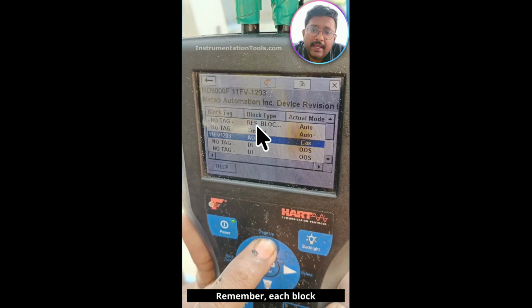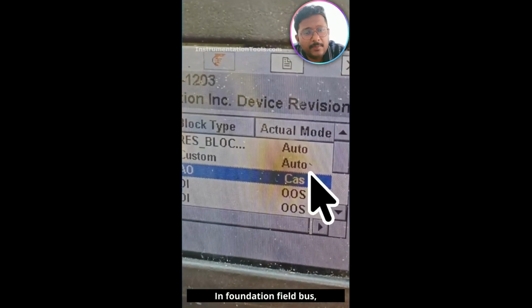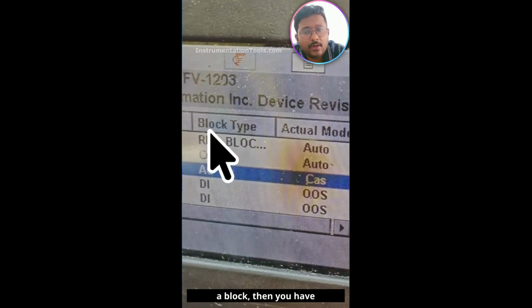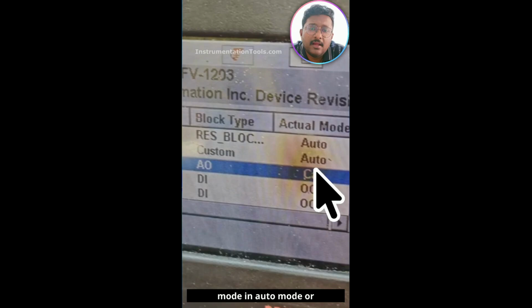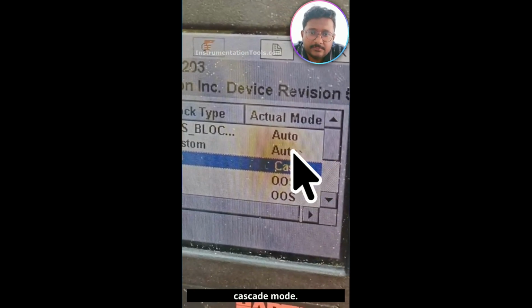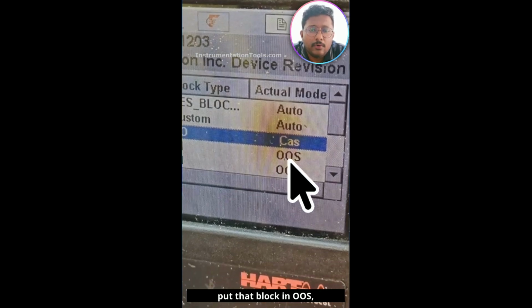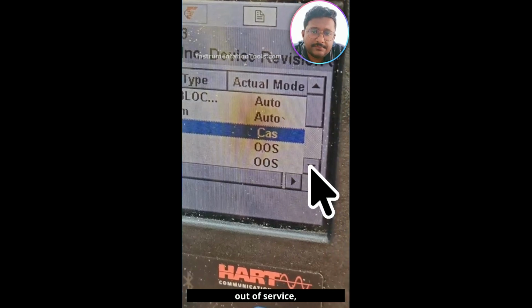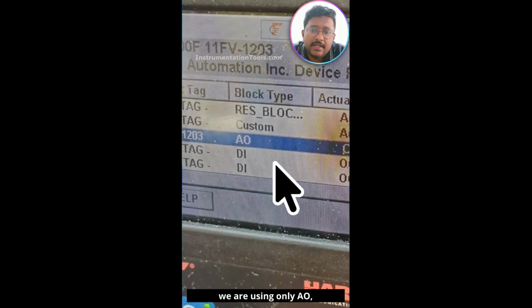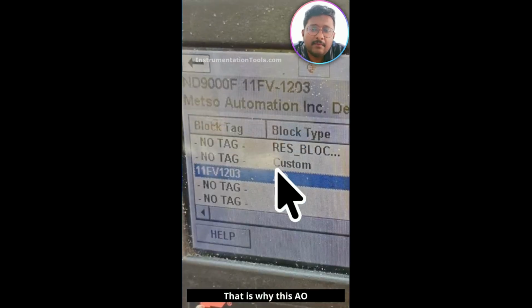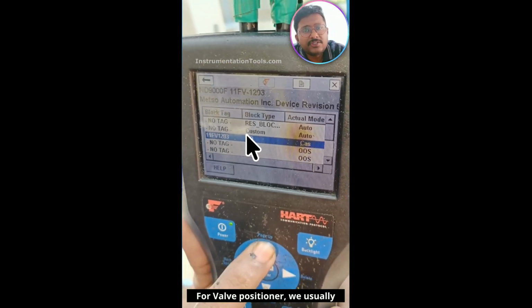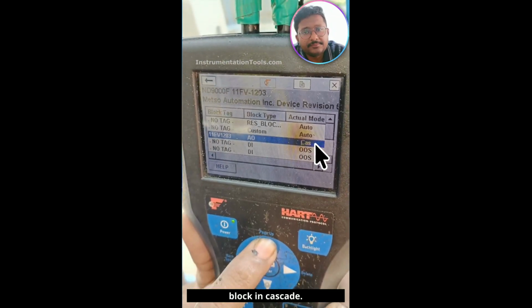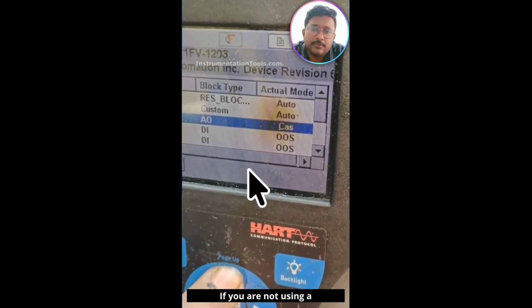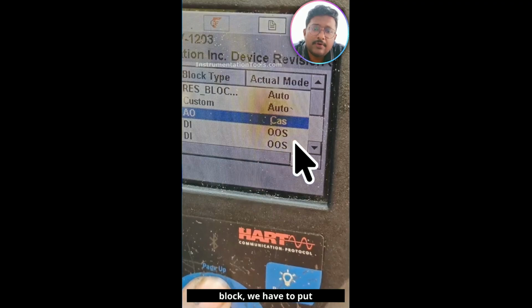Remember, each block has a mode. In Foundation Fieldbus, whenever you are using a block, you have to put that block in auto mode or cascade mode. If you are not using a block, then you have to put that block in OOS, out of service. In this valve positioner, we are using only the AO block type. This is an analog output instrument. That is why this AO block is enabled. For a valve positioner, we usually put this block in cascade. Other blocks we will put in auto mode. If you are not using a block, we have to put it in out of service.